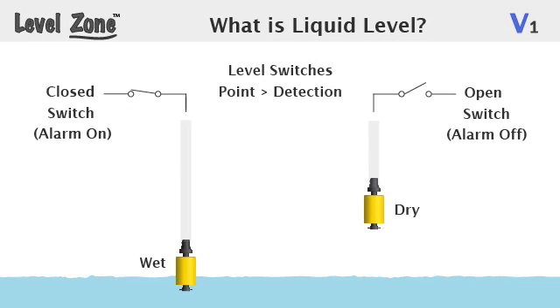Point sensors detect the presence or absence of liquid at their point of installation and provide a switch output that indicates their wet or dry status. These sensors are called level switches and are typically used for basic alarm and control functions.